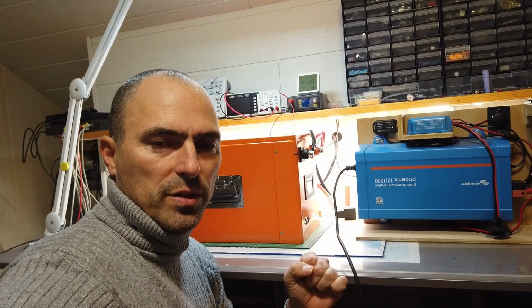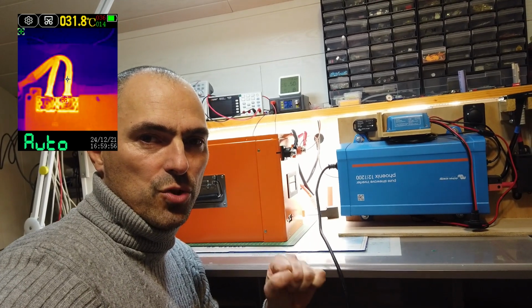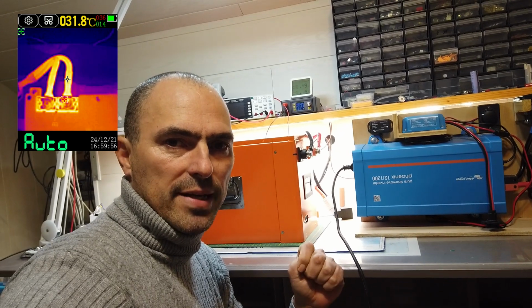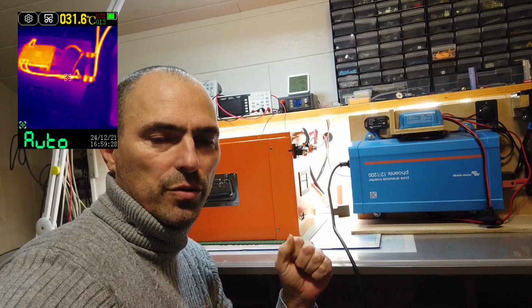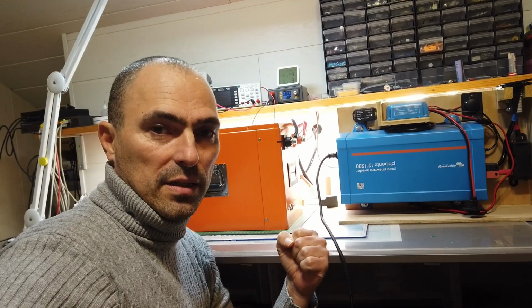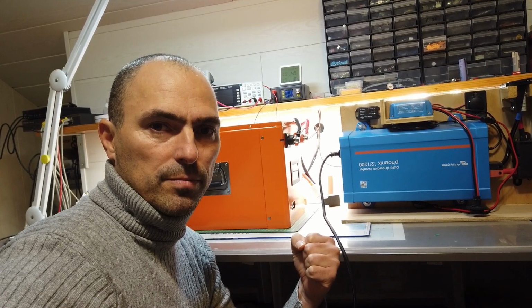I just finished the load test and I can conclude that everything works fine. There are no issues. Cables are not getting too hot. The highest temperature I've seen was like 32 degrees. So everything is well dimensioned, and congratulations to UBP Power. They did a great job.